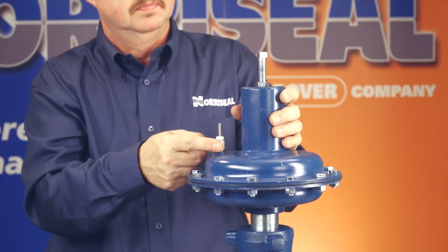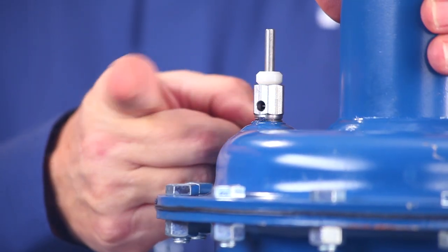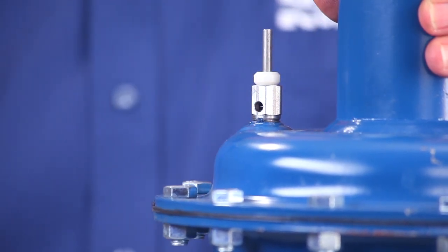While you're looking at the vent hole, put your finger over it, then remove it. If you detect gas escaping from the vent hole, you know that your diaphragm needs to be replaced.